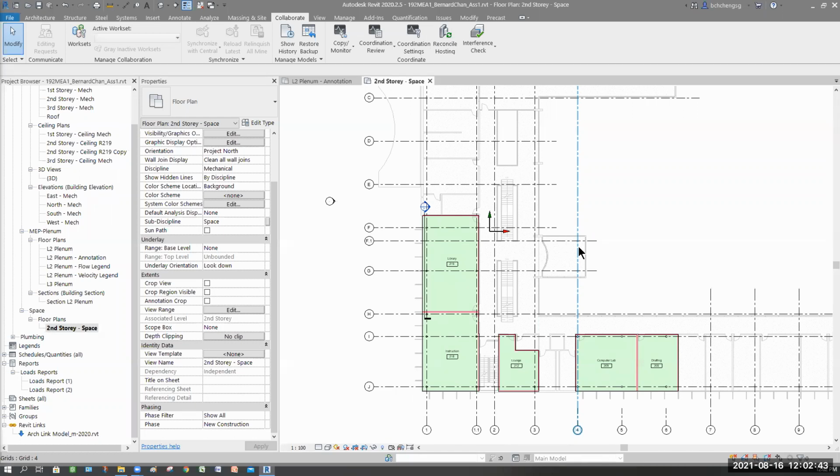So floor to floor height, the clear ceiling height, the false ceiling, all those things. And structure, what is the beam size, the depth, which is called the height. They call it B and H. So these are things you need to know. If you don't have it, how am I going to design? So it's very crucial, especially the basement. Always keep this in mind, because Archi always do not show beams, so it's quite misleading when it comes to design. So it's a must to get the structural model.